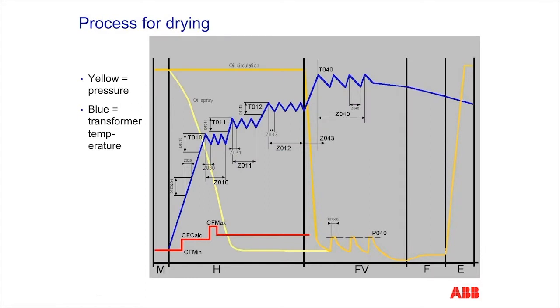As the transformer may not contain oil, high voltages cannot be applied to the transformer to generate the required current in the windings to produce the heat necessary to dry. The transformer needs to act as a transformer to induce current flow in the low-voltage windings to facilitate the heating process. The low-frequency heating approach allows one to get the necessary current flow in the high-voltage windings with less than 1% of the voltage that would be required at the nominal frequency of 60 Hz. Even at a low frequency, current flow is induced in the low-voltage windings, thus producing heat for the drying process. With a voltage in the range of hundreds of volts rather than thousands of volts, arcing within the transformer becomes non-existent. Mobile power is capable of supplying the electrical requirements of the low-frequency plant running under the constraints mentioned.